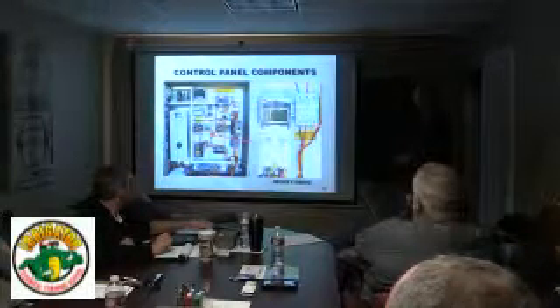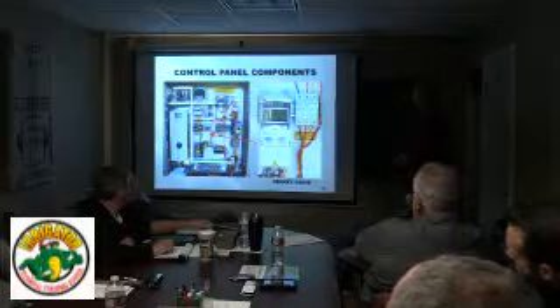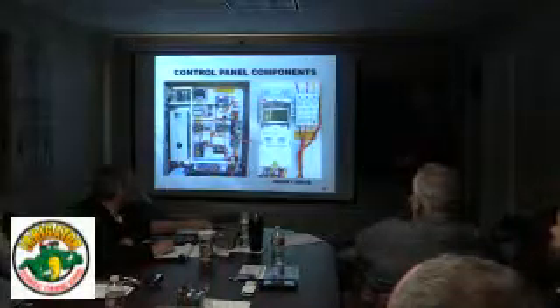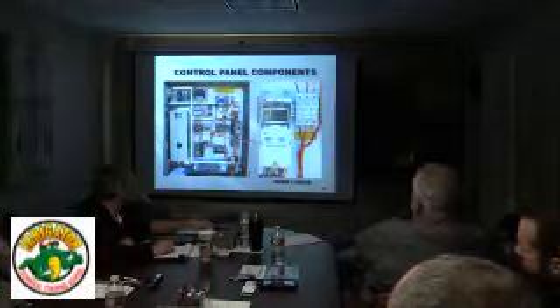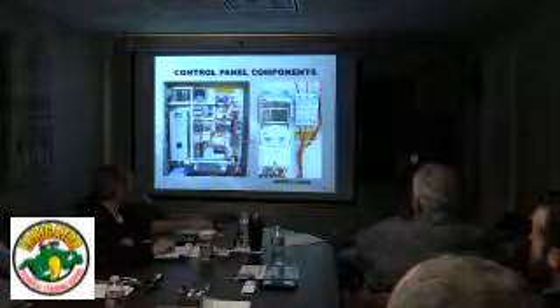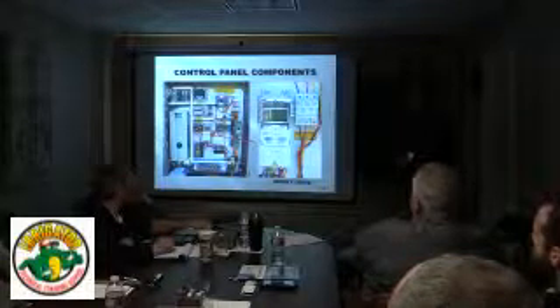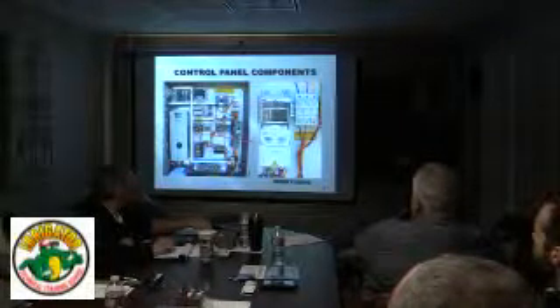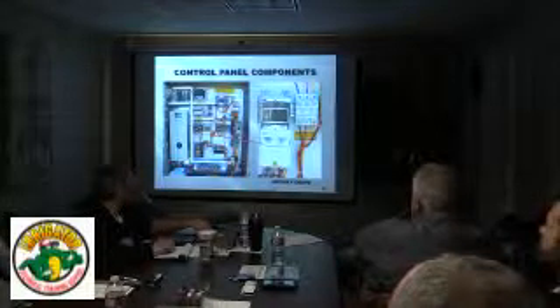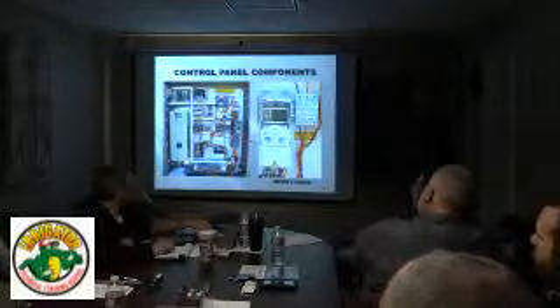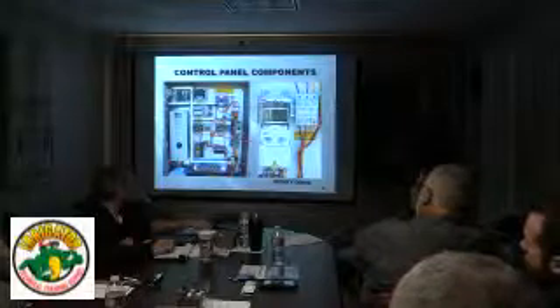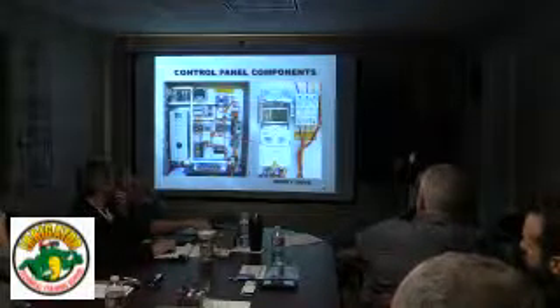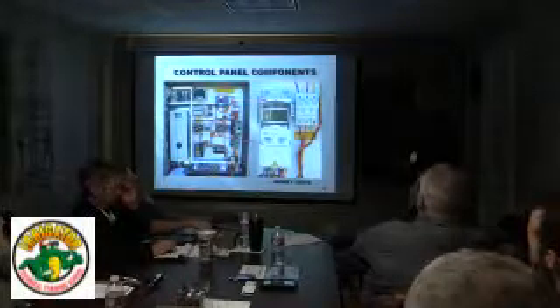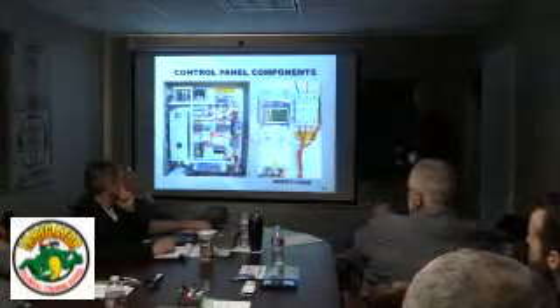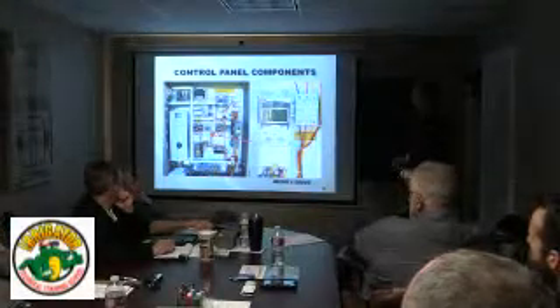Then there's the jockey pump, the pony pump, VFD. A lot of our systems will use a VFD on the jockey pump also. Note that the keypads look identical. Even the parameters in this, this is an ACS 350 and that's an ACS 550. They're different models of drive, but the keypads will interchange. The parameters are the same, so once you know one, you know the other one.